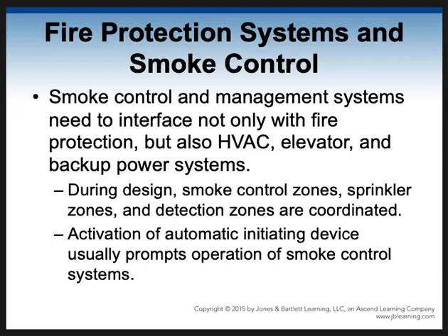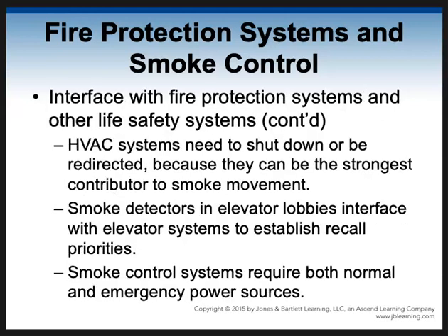So that activation is going to be tied into the alarm system, and the alarm system is going to turn on the smoke control system. The sprinklers are going to be turned on by the heat, and all of these things, they're all going to work together. So a lot of times, the smoke control system going off and the sprinklers turning on needs to shut down the HVAC system so they're not feeding air in. So HVAC systems can be used as part of it, and they can be a deterrent to it.